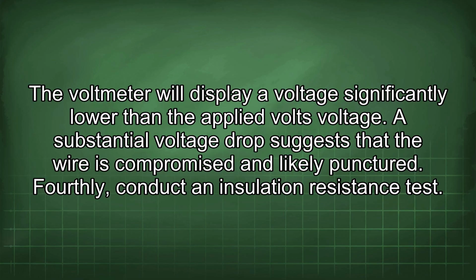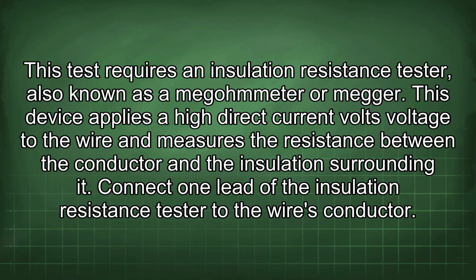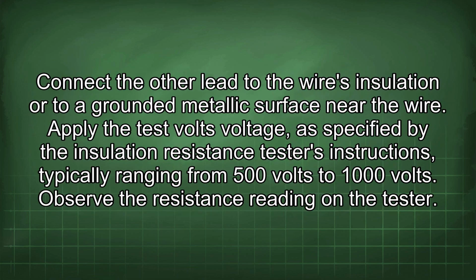Fourthly, conduct an insulation resistance test. This test requires an insulation resistance tester, also known as a megohmmeter or megger. This device applies a high direct current voltage to the wire and measures the resistance between the conductor and the insulation surrounding it. Connect one lead of the insulation resistance tester to the wire's conductor. Connect the other lead to the wire's insulation or to a grounded metallic surface near the wire. Apply the test voltage, as specified by the insulation resistance tester's instructions, typically ranging from 500 volts to 1000 volts. Observe the resistance reading on the tester.